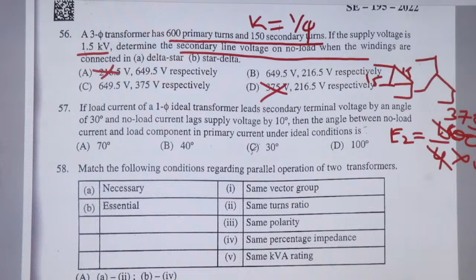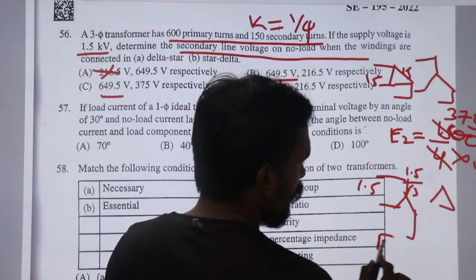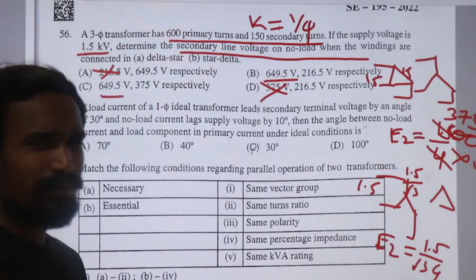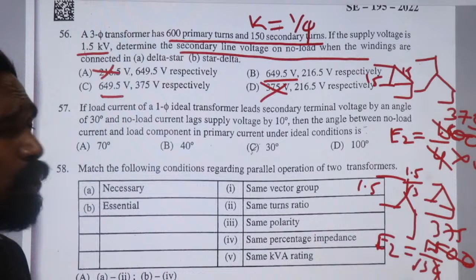What about star delta? In star, the line voltage is 1.5, then the phase voltage is 1.5 upon root 3. Then E2 is equal to 1.5 upon root 3 upon 4, that is 1500 by root 3 by 4, which is 375 by root 3. That is the phase voltage of delta. The phase voltage of delta is 375 by root 3.